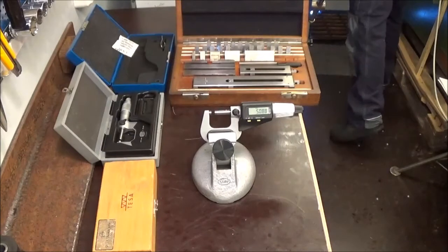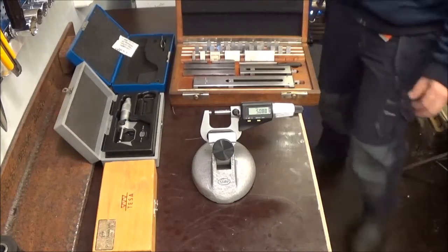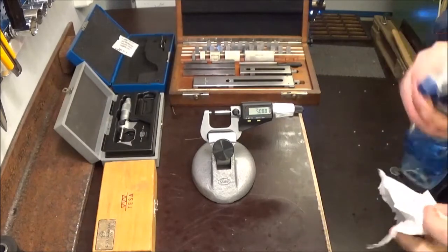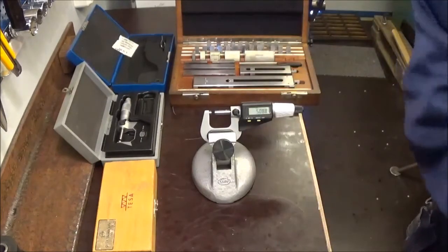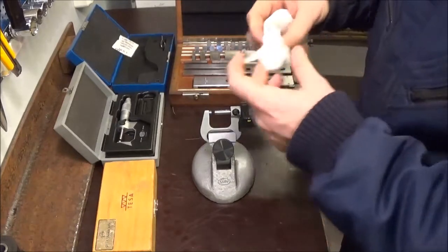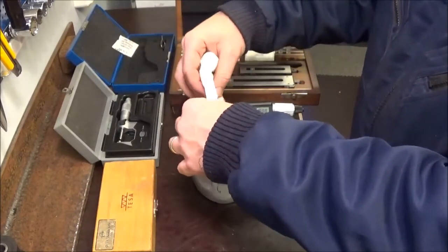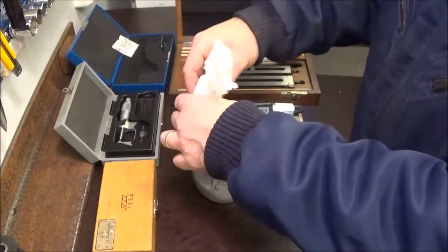The problem I've found is when people are zeroing these out, there's always a bit of crud stuck in the anvil. This window washing liquid will get rid of any schmoo that might be stuck there.